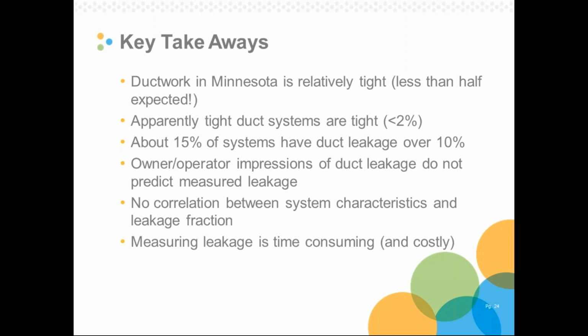And unfortunately, one of the real things that we found was that there's not a big correlation between system characteristics and leakage fraction. Essentially, at the end of the day, it means that duct leakage comes from a variety of reasons, but it comes down to the way a specific system was built by a specific crew at a specific time. In fact, even in the same building with systems built ostensibly by the same crews around the same time, we find leakage fractions varying by a factor of 2.